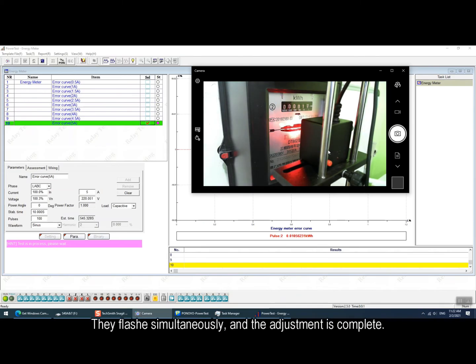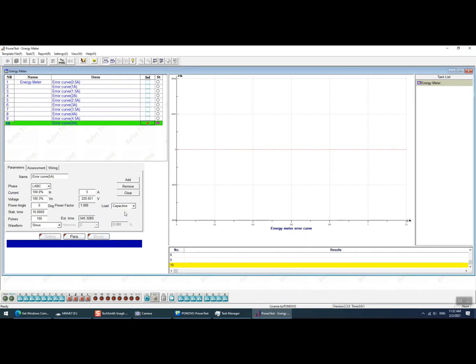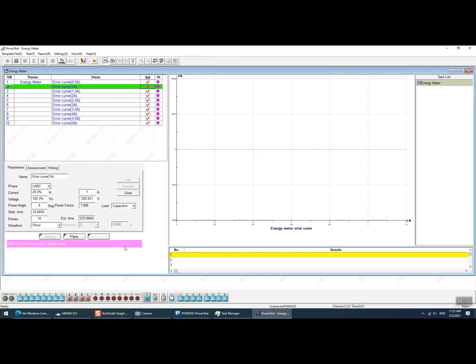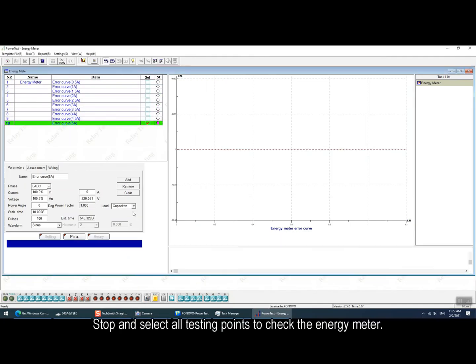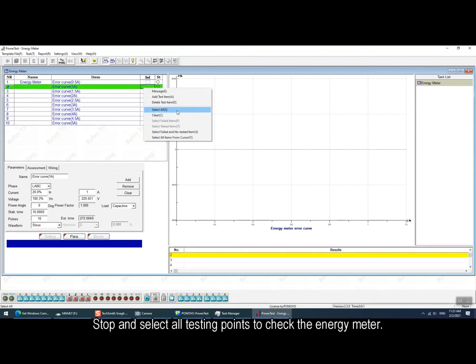Then wait for the line of the disk to pass and see if the scanning head flashes in the same time or not. If it flashes simultaneously then it means the adjustment is completed. Then we can stop the injection and select all the testing points to check the energy meter.